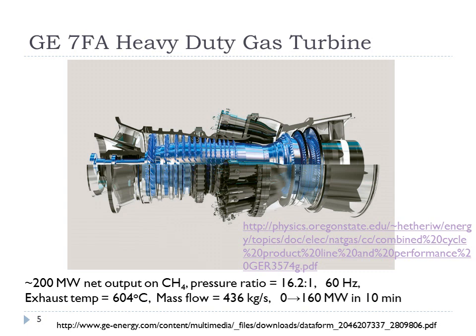This particular gas turbine has about 200 megawatts of output when run on natural gas, with a pressure ratio of 16.2 to 1, meaning the pressure in the combustor is about 16 atmospheres. It's a 60 Hz version for the US. The exhaust after the turbine expander is about 600 degrees Celsius, and nearly half a ton of gas flows through it per second.